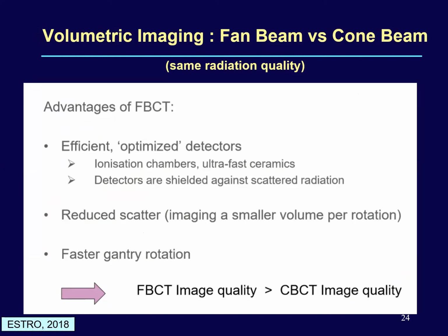Remember that the fan beam geometry can rotate faster, and because it images a smaller volume per rotation, there is reduced scatter, hence superior image quality. A superior image quality from the same source, maybe KV or MV, is always seen with the fan beam geometry rather than the cone beam geometry, because in cone beam geometry you have larger scatter from the patient, degrading the image quality. Nowadays you have a lot of scatter correction algorithms in the software. In spite of that, the fan beam geometry offers superior image quality.